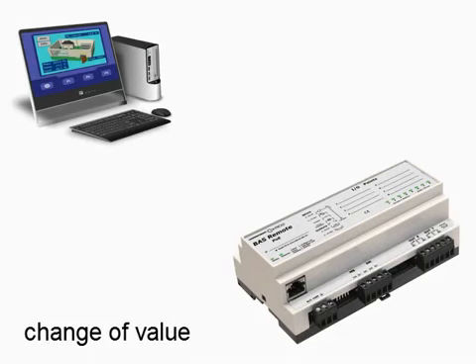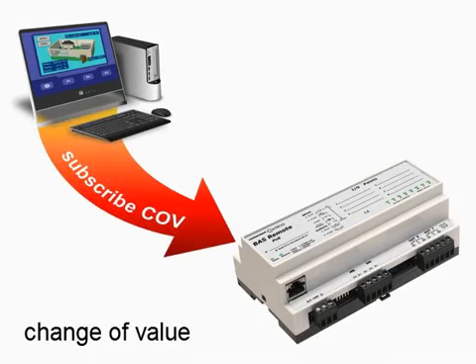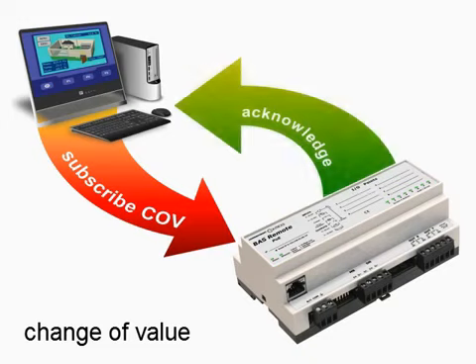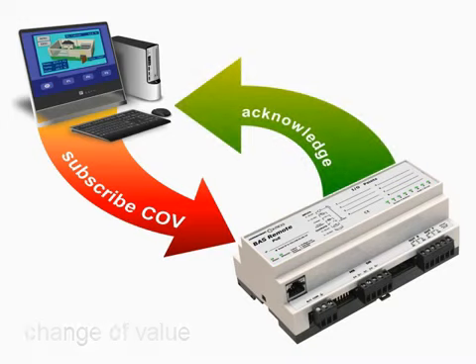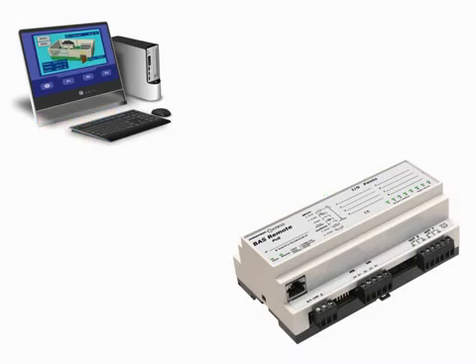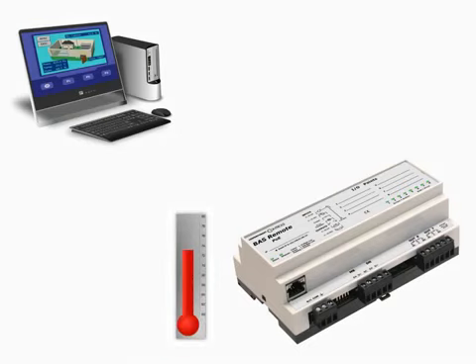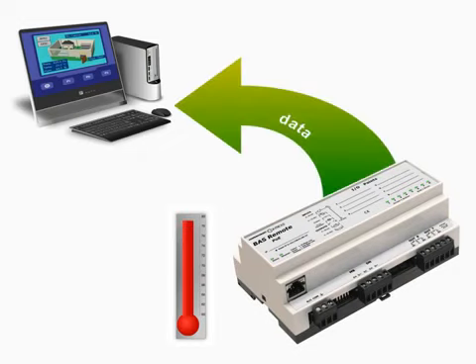To minimize data traffic, change of value, COV, is supported where only values that change above a defined limit are sent. This minimizes network traffic. A client subscribes to the server device, and the server monitors the property and reports when the subscribed property exceeds the threshold range.